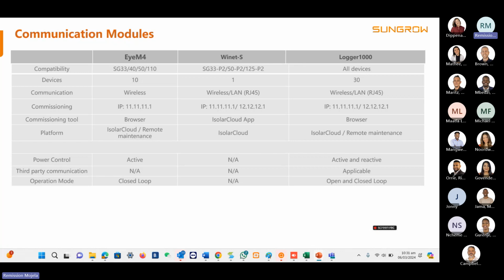It also offers you active and reactive power control. And then third-party communication is applicable on the Logger 1000. It gives you open and closed loop operation. By third-party communication, I mean you can get any controller and you still have access to the iSolar Cloud and the remote maintenance. So you can still go to the iSolar Cloud and change whatever settings you want on any particular inverter on site, while the inverters are still controlled by a third-party controller. The Logger 1000 provides you that capability. None of our controllers except for the Logger 1000 will offer you that capability.